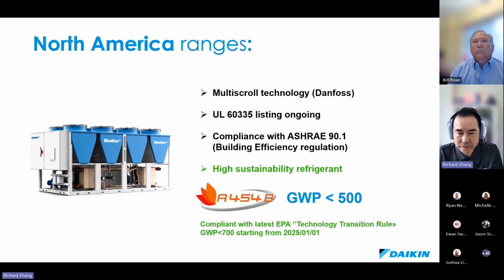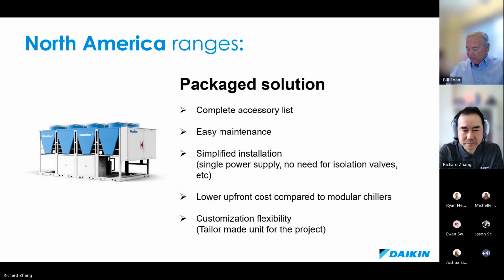In the previous slide you probably noted that we are doing both in Europe, but when we come to North America we have to make a choice, because the government body here requires GWP less than 700, and R32 is too close to that limit from our standing.